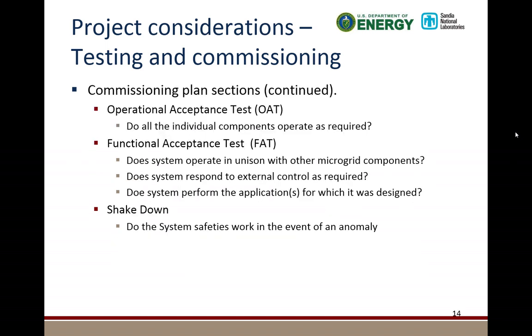And continuing on with testing, then you have your operational acceptance testing, your OAT. That's, do all the individual components operate as required? Then your functional acceptance test: does the system operate as a system with other microgrid components? Do you have the right control? Does it perform the applications that it was designed to do? And then a shakedown portion, and that is basically shutting the power off, doing the anomaly type things to see that the system shuts down in a controlled manner and restarts in a controlled manner, and that all your safeties operate, all your annunciations operate, etc.